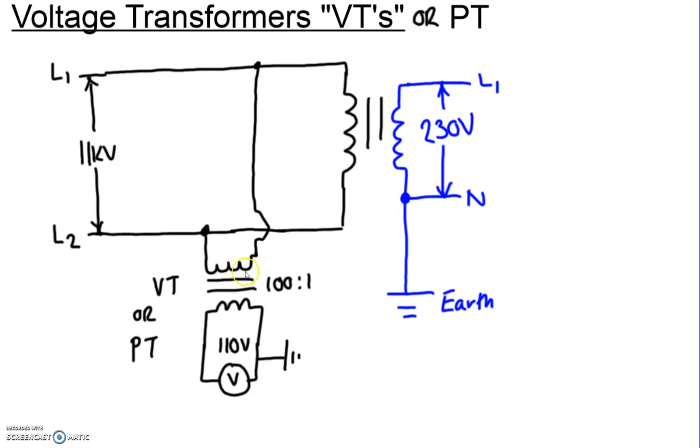So this is our primary feed. And then we have a voltmeter, 110 volt voltmeter. This could be a digital multimeter plugged into the transformer, or it could be just a moving coil meter, panel meter. The ratio is 100 to 1. So effectively on full load, 11 kilovolt, we will be displaying 110 volts.